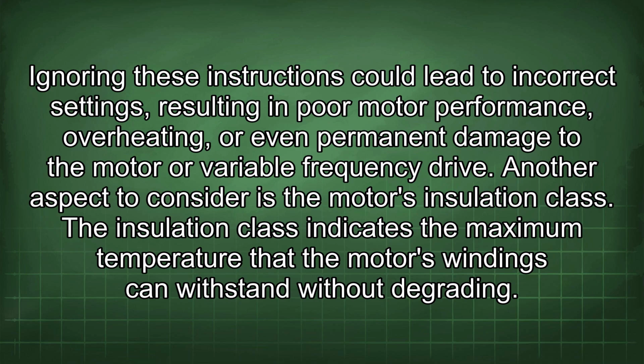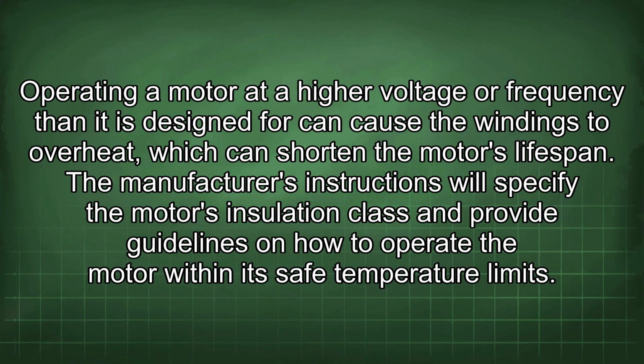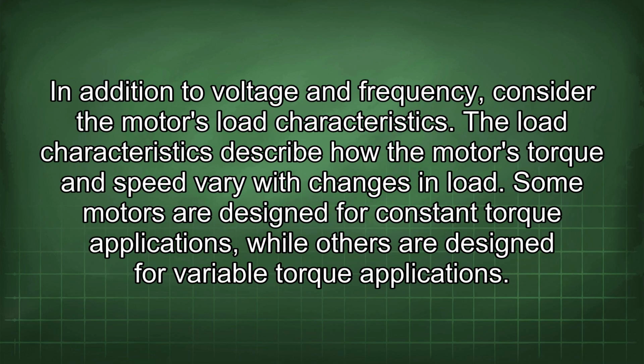Another aspect to consider is the motor's insulation class. The insulation class indicates the maximum temperature that the motor's windings can withstand without degrading. Operating a motor at a higher voltage or frequency than it is designed for can cause the windings to overheat, which can shorten the motor's lifespan. The manufacturer's instructions will specify the motor's insulation class and provide guidelines on how to operate the motor within its safe temperature limit.